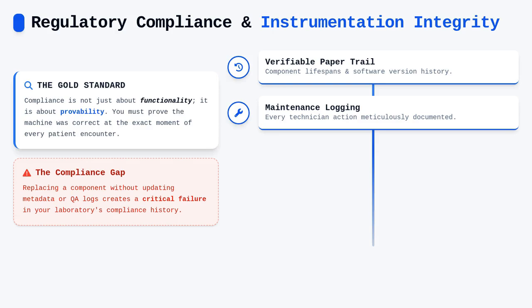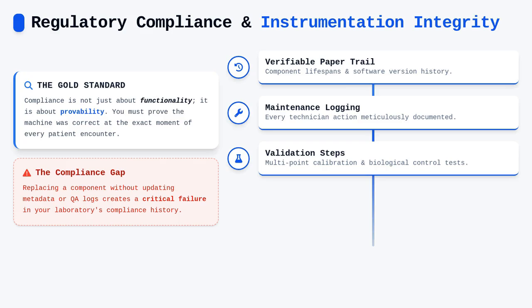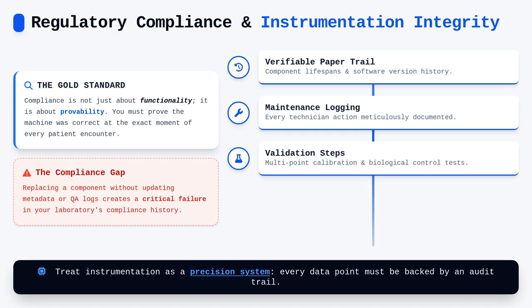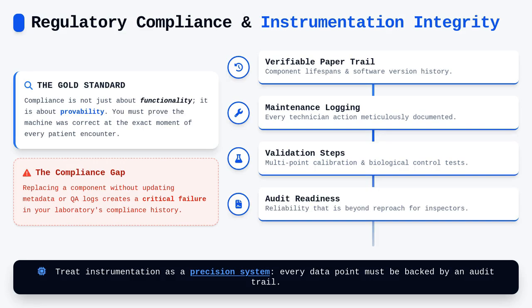This documentation must include the specific validation steps taken after an update, such as a multi-point calibration check or a biological control test to verify physiological measurement stability. Maintaining this level of detail requires that you treat your laboratory instrumentation as a precision system, where every recorded data point is supported by an audit trail of maintenance. By adhering to these schedules and technical instructions, you build a foundation of reliability that is beyond reproach to both internal auditors and regulatory inspectors.